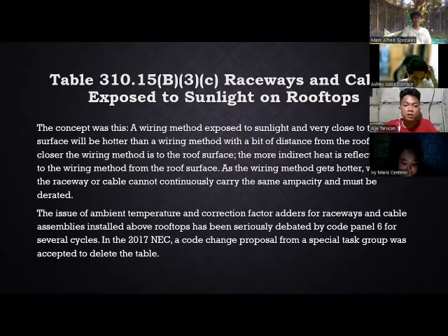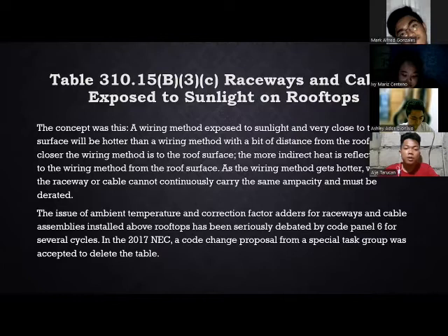The closer the wiring method is to the roof surface, the more indirect heat is reflected back to the wiring method from the roof surface. As the wiring method gets hotter, wiring in the raceway or cable cannot continuously carry the same ampacity and must be derated. The issue of ambient temperature and correction factors for raceway and cable assemblies installed above the rooftop has been seriously debated by Code Panel 6 for several cycles. In the 2017 code, a change proposal from a special task group was accepted to delete the table.